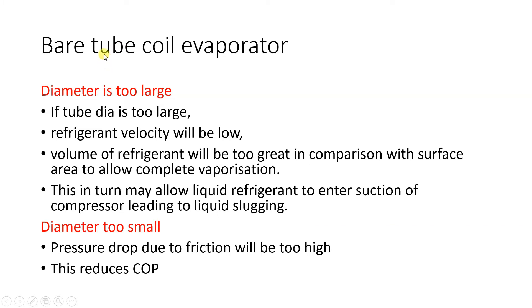Regarding the diameter of bare tube evaporators: if the diameter is too large, using the mass flow rate formula ṁ = ρAV, with constant mass flow rate an increase in area means the velocity reduces. So refrigerant velocity will be low, and the volume of refrigerant will be too great relative to surface area to allow complete vaporization. This may allow liquid refrigerant to enter the compressor suction, leading to liquid slugging. If the diameter is too small, the frictional pressure drop will be too high, reducing the COP.